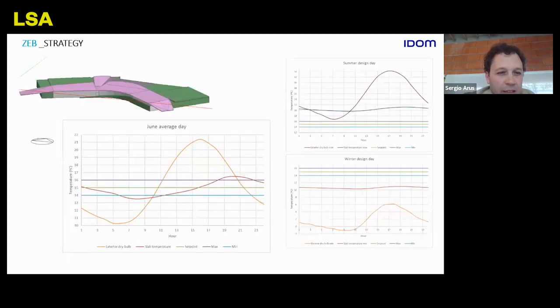This is what we've done with these energy simulations. With the TABS and the thermally activated structure, with the set point at 15 degrees, we can keep it quite well. The red line shows how we are performing—quite close to the set point, within plus or minus 1 degree.